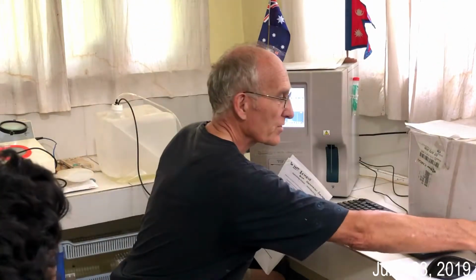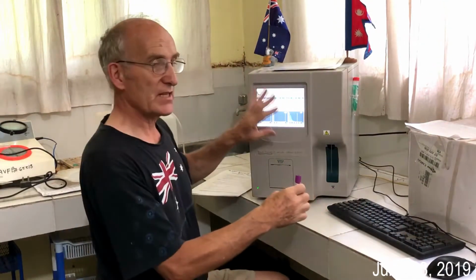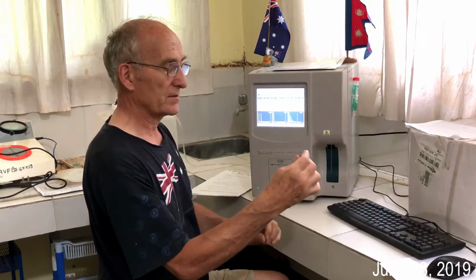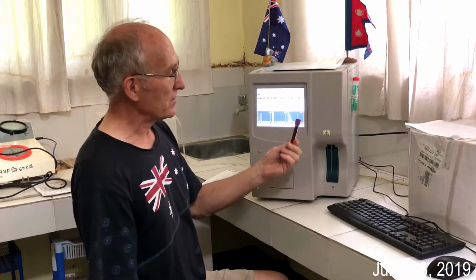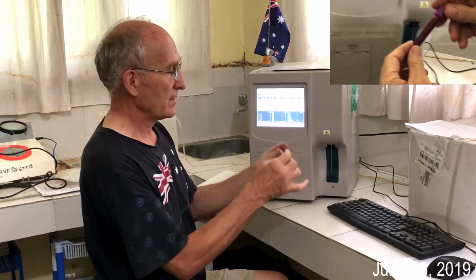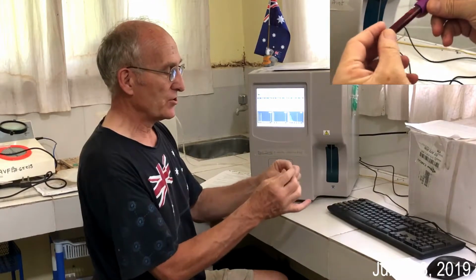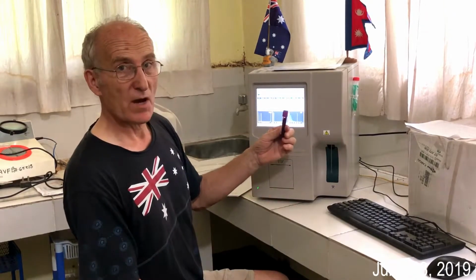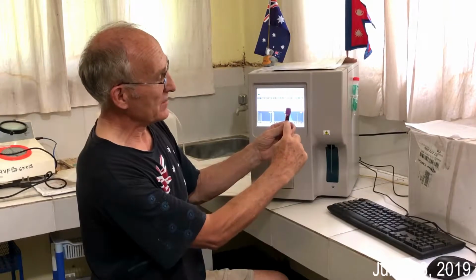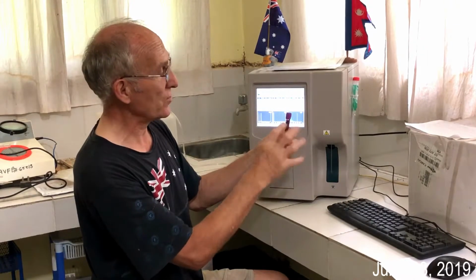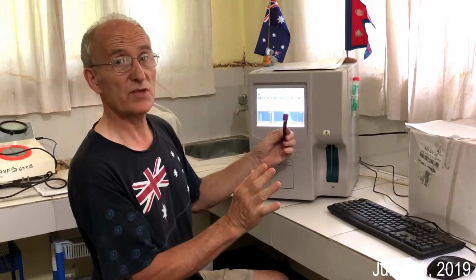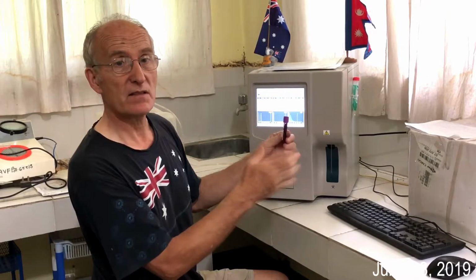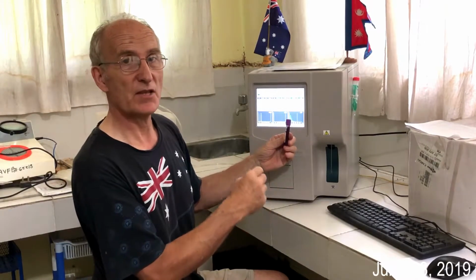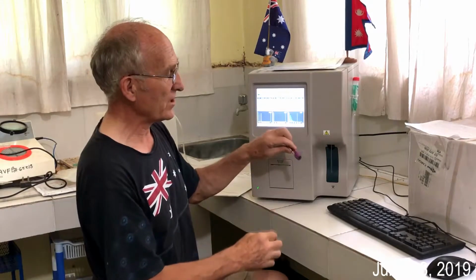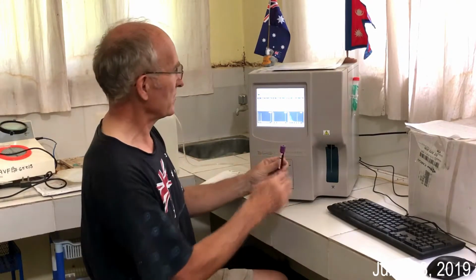Now, this part is important. We've entered now the patient details and we have the sample here. This is an EDTA sample to prevent it clotting. It's important to gently rock the sample. Why? If the sample has been sitting like this for a while, the blood cells will have gradually fallen down to the bottom. So if you don't gently rock, you get a false reading. If you shake vigorously, you will break up some of the cells and therefore you don't get an accurate reading. So only gentle rocking is required to mix the sample.